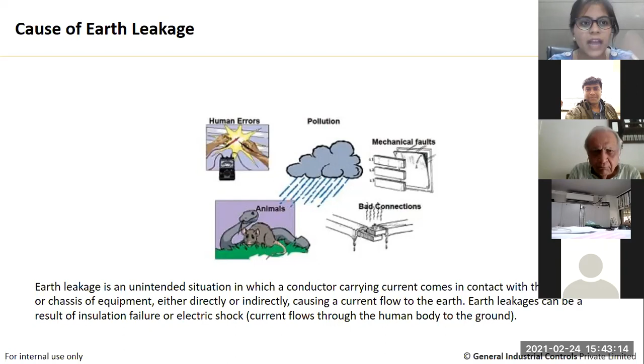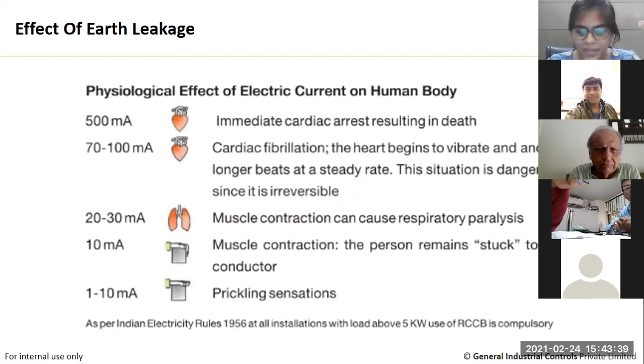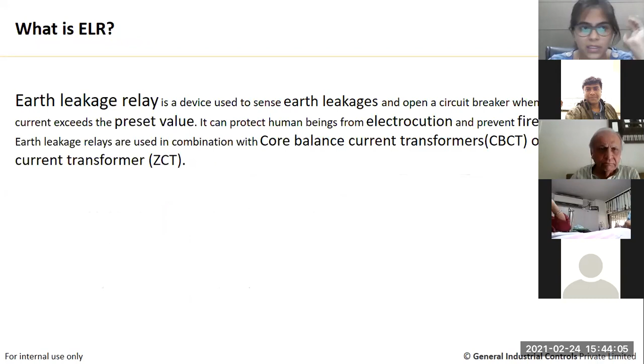Now what happens with that leakage? A small amount of leakage current is permissible. It is okay for a human being, or for the machinery. But if it goes beyond a certain level, let's say 30 milliampere, then it is very dangerous for any person. They may get a shock, or it can result in death as well. So here comes our last device, which is the earth leakage relay. As its name suggests, it senses the earth leakage and trips the circuit. This device is always used with CBCT, that is, core balance current transformers.